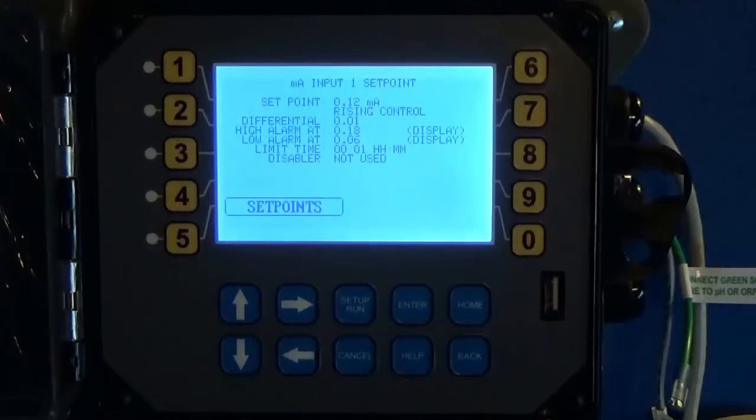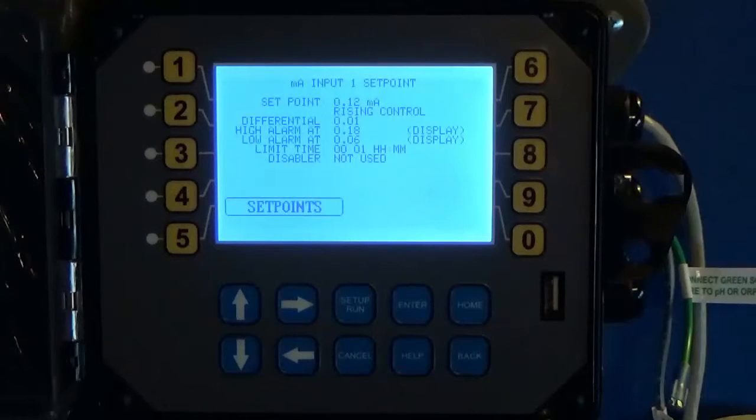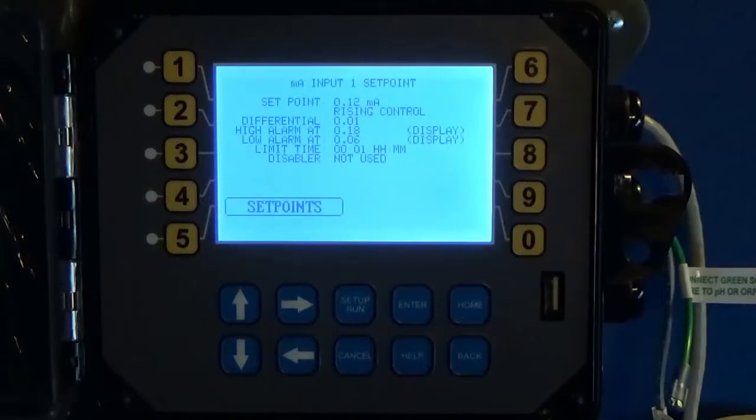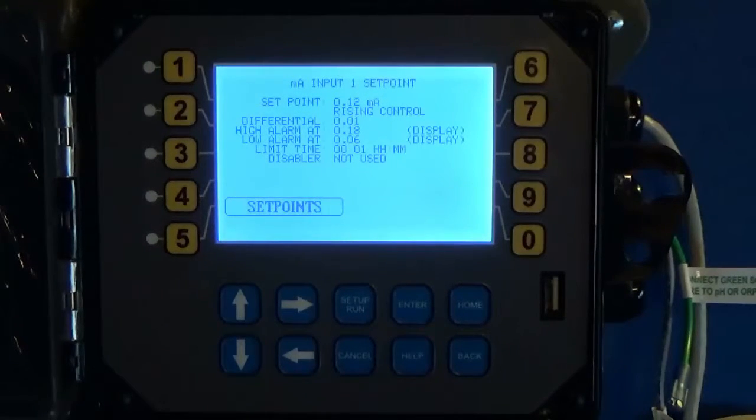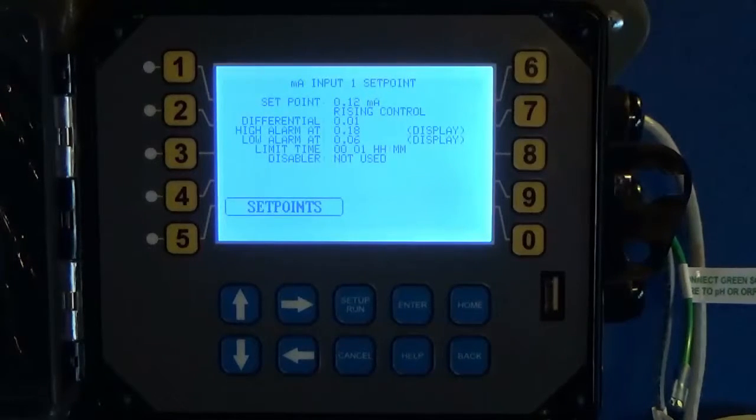Disablers are very important for milliamp inputs because the flow switch does not automatically disable your milliamp input, simply because it's not tied to that specific system. It could be some independent thing.